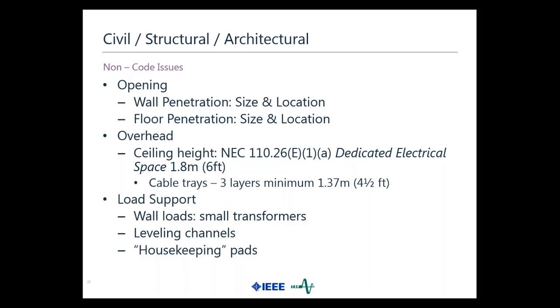And I threw that little blurb in there to make you think about it. That's not a lot of room. You may want more than that 6 foot, because if you've got a cable tray, 3 trays with 6-inch side barriers, and you want at least a foot between them for access to the cables in the tray, you already got to 1.37 meters, 4.5 foot.